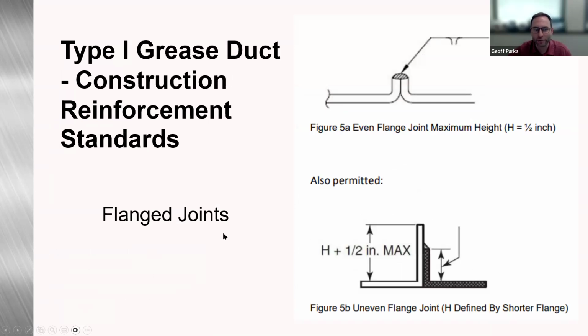And then we cover flange joints within the duct construction reinforcement standard for grease duct. Figure 5A is the even flange joint, and again, that's a maximum height of 1/2 inch. Also permitted is what we're calling the uneven flange joint, which I showed you earlier out of the NFPA 96. So this is an uneven flange, and the height of the uneven part is going to be 1/2 inch or H plus 1/2 inch.